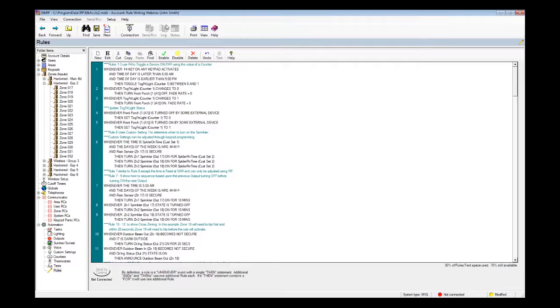Another question we got in, can you have multiple things connected to the M1 at the same time? Okay, yeah, I think I understand the question. When ElkRP connects, all other connections, M1 to go, the third-party smartphone apps, other automation systems, those connections are suspended while RP is connected. But if RP is not connected to the system, you can have 30 other connections. You can have the M1 to go, the Keypad, M1 touch, the touch screens. You could have 30 of those connected at one time.